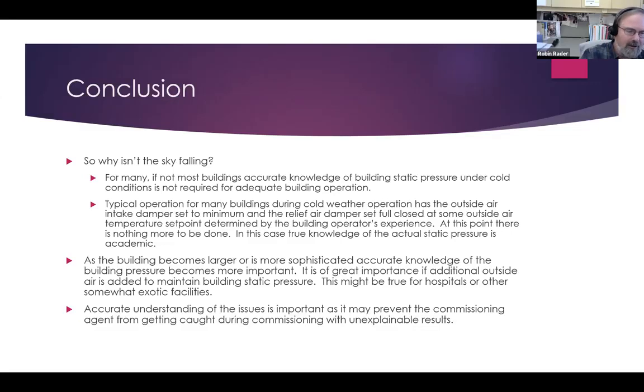I did a little calculation. The Corps of Engineers is starting to require building envelope leakage testing. I think the number they allow is 0.4 CFM per square foot. That's actually quite a bit of air, and buildings in Alaska are built tighter than that. A tighter criterion is 0.15 CFM per square foot. But anyway, you need to bring in enough outside air to blow against your building to maintain building static pressure. And if you're relieving air through your HRV, this might not be happening. And so you might have a negative building just on that basis.